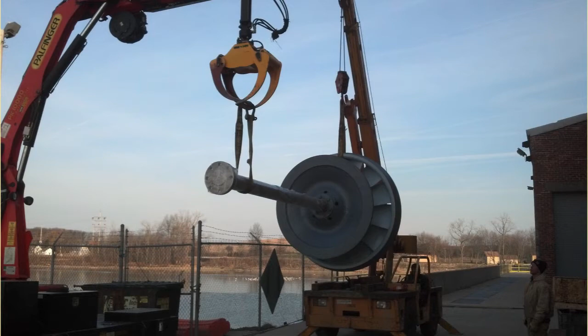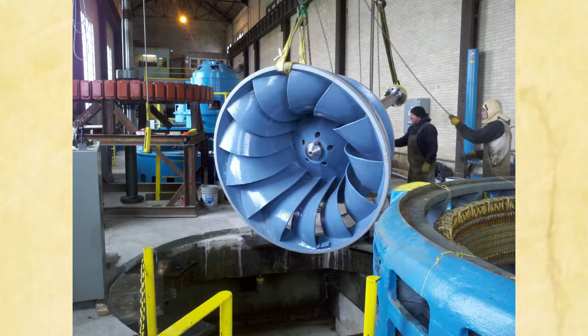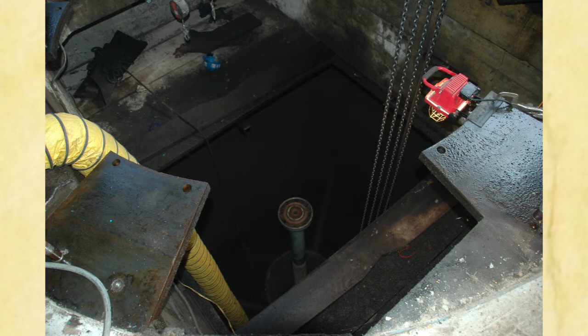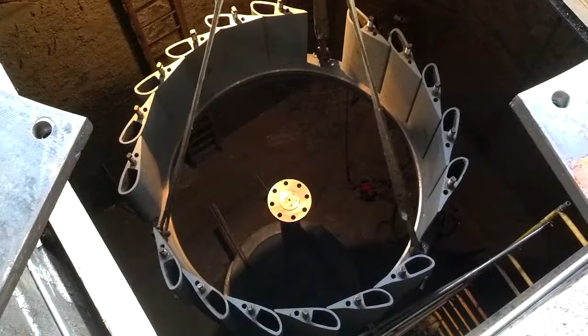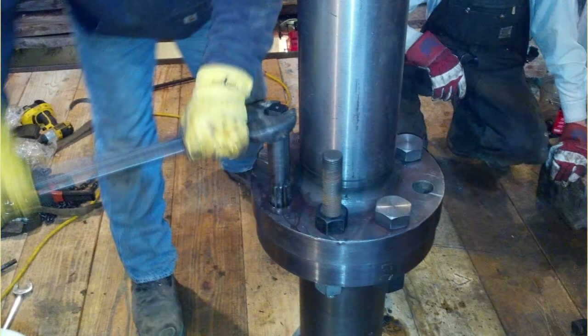And then we had a ceramic coating put on those runners also to give them a lot longer life and to improve the efficiencies. Basically, the rebuild started from the bottom all the way up through the machine. We stripped everything out, then started reassembling with new machine parts, and basically we changed some of the design changes that were put in when the machines were reinstalled in this plant in the 80s. We had some different design that the company who reinstalled them tried that didn't seem to work too well. So we took the machines and put them back to their original design.